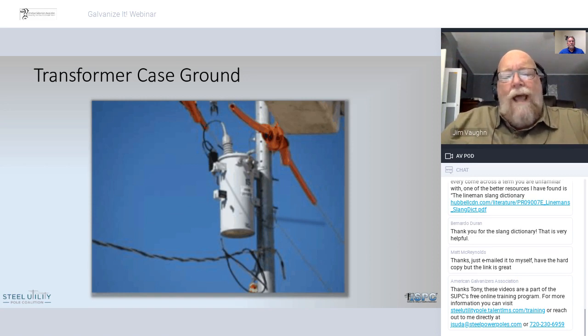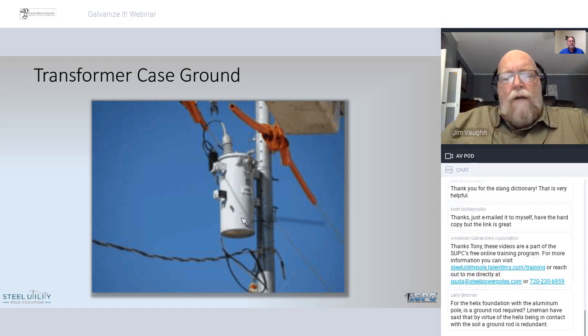The steel poles have an added benefit in that the conductivity of the steel pole is so good that when you lose that ground connection, it doesn't happen often, but it does, the steel pole almost always assures a ground path connection to ensure that this case will not become energized. So that's one of the big things that I thought of very first thing when we started hanging transformers on steel poles: the integrity of the bonding and grounding connection between this energized apparatus and the steel poles. I thought I'd add that in there as both a sales point for the steel pole manufacturer, and it's also good information for linemen to know about the risk associated with a lost ground lead on a transformer on a pole.